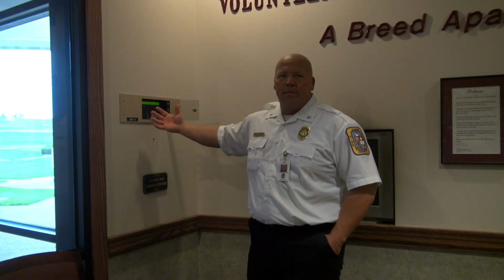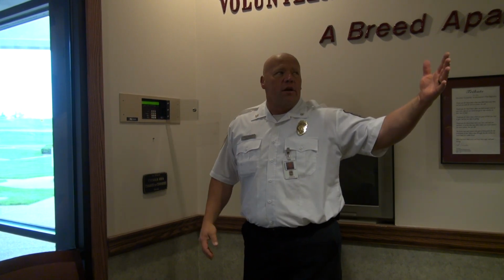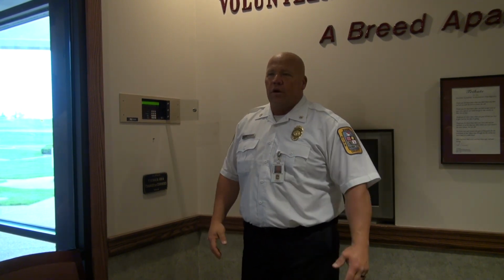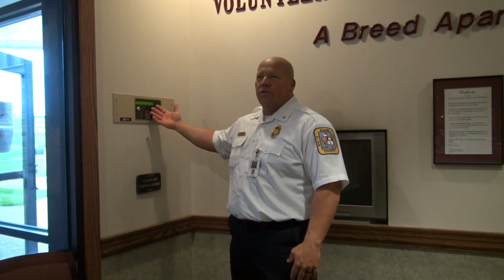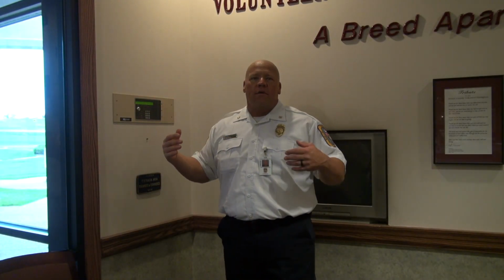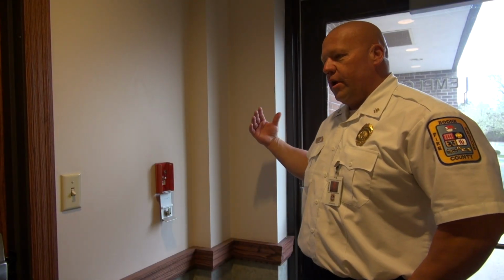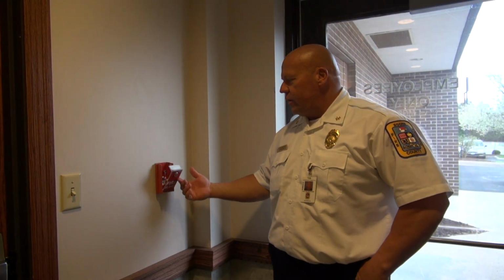So this is going to remain in alarm, but you've now shut off the alarm horn strobes throughout the building so you can walk around. So the alarm panel tells us reception, west entrance. So we're going to go and find out which pull station was actually activated and make sure it's still in that position.